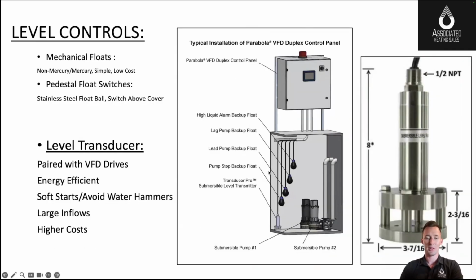Your last option is a level transducer, and it's typically paired in a system that should have redundancy in its controls, because you can see how these transducer panels that are typically variable frequency drives have backup floats. So you have 2 ways to do this. So if this transducer fails, you have backup float operation, and you have an alarm, and you can replace the transducer or see what's going on.